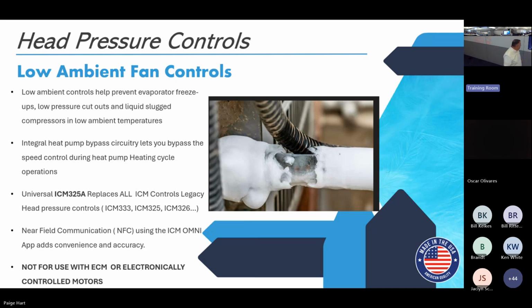We have special heat pump bypass circuitry on this device. In a heat pump, when you're in heating mode, you don't want to regulate the speed of the fan. You want to push as much air past the coil as possible in that mode, so we can bypass it when you're in heating. But this control is smart enough to know when you're not in heating and you want to go into cooling again, because this is low ambient control for allowing you to run air conditioning in the middle of the winter, and refrigeration. So it knows by sensing the reversing valve direction that, okay, I'm in cooling now, let's go into variable speed. But if I'm not in cooling, I want to just bypass. So it has that smarts.